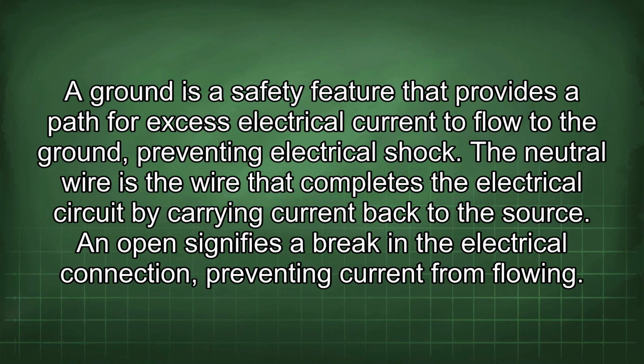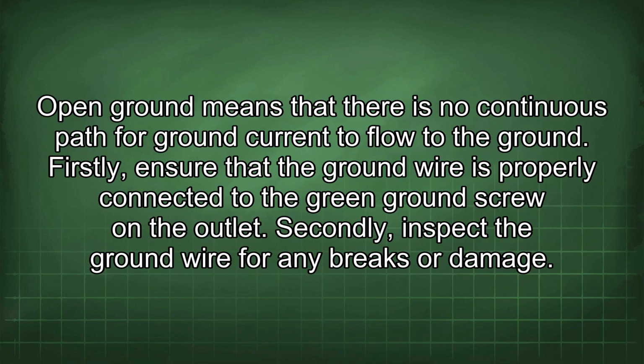Ground is a safety feature that provides a path for excess electrical current to flow to the ground, preventing electrical shock. The neutral wire is the wire that completes the electrical circuit by carrying current back to the source. An open signifies a break in the electrical connection, preventing current from flowing. Open ground means that there is no continuous path for ground current to flow to the ground.